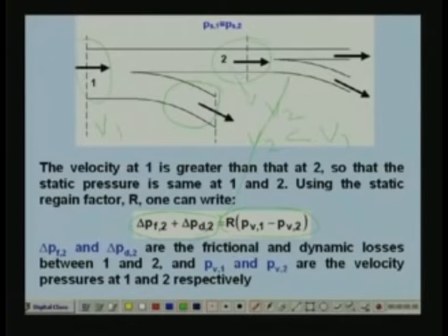Okay. So, you find that because you are balancing exactly the drop in velocity pressure with that of the losses, the static pressure at point 1 and 2 will remain same. That means PS1 will be equal to PS2, right. So, what is section 2? Section 2 is nothing but the upstream for the next downstream section and the branch.